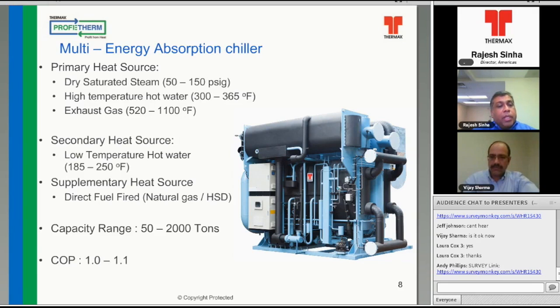So I deviated a bit, but staying on the multi-energy absorber, there could be a supplementary heat source which could be added together with the primary and the secondary heat source, and that could be in the form of direct natural gas firing or any other fuel. This has a capacity range of 50 to 2,000 tons, and a full load COP in this case would be about 1 to 1.1. Now, remember that absorbers would have IPLVs which are close to about 25% higher than the full load COPs we are demonstrating to you on these slides.